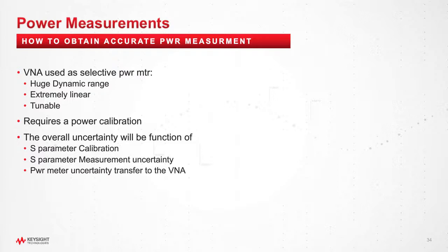So let's go into a little more detail on how we compute the power meter measurement. For example, the power meter has a measurement model which is traceable to the microcalorimeter, in this case of NIST, and then it goes toward your device and your sensor. You have uncertainty contributions, which are given by the power meter reading, the sensor efficiency, the power of the generator, and so on. With the VNA, this is the model that you have to use. You have the reading of the VNA, in this case a_m1, and you have gamma in, and you have the source match in this case.